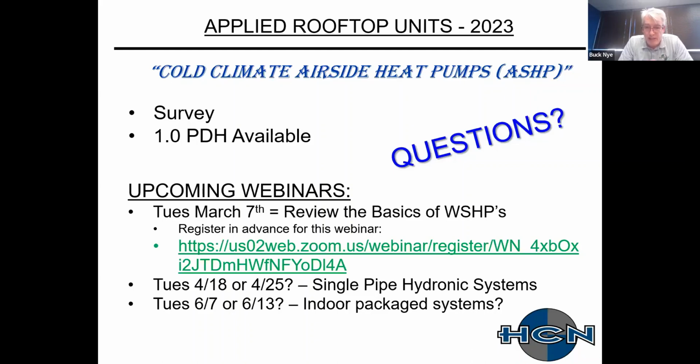What is the tonnage and CFM available for packaged rooftop units? Can it be used for lab applications with VAV and 100% outside air systems? So I presume you're asking about the cold climate. As the slide said at the end, the tonnage that we have available currently is up to 50. In terms of CFM, that depends on whether it's a constant volume or a DOAS system. As you know, a DOAS system has much lower CFM per ton criteria.